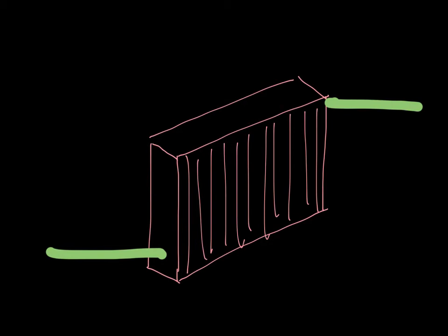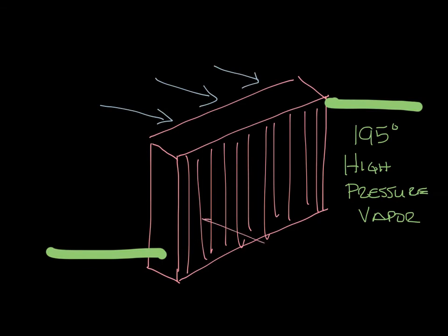So coming into the condenser, you have 195 degree high pressure refrigerant vapor. Air passes through the fins of the condenser and cools the 195 degree vapor down, which causes it to condense back into a liquid. The refrigerant leaves the condenser as a 110 degree liquid refrigerant. And the air that passes through the condenser warms up. So that's the condenser.